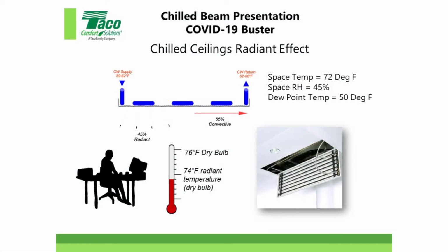So here's a picture. Unfortunately, you can see on the bottom right it's dropped down, and it just has some tubing on it. Maybe it could be copper, it could be some plastic tubing, and that's just above the ceiling. The chilled water that goes into that coil has to be above the dew point. If you notice in the top left-hand corner, it says 59 to 62 degrees. It's so important. If it's not above the dew point, you will get dripping, or some moisture in the system. So that's one of the critical parts of it, no matter what type of radiant cooling you're putting in. That's why a lot of people are scared of this type of system, especially in very humid climates.